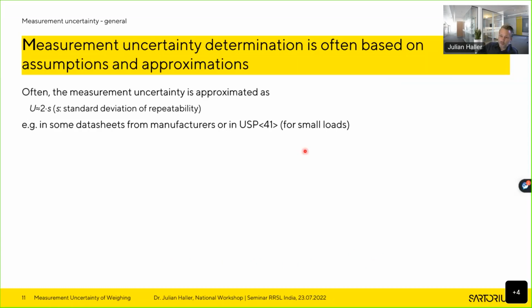And what you've probably seen in, for example, data sheets from manufacturers, or if you're familiar with that in chapter 41 of the USP for small loads, is that as a rough approximation of the measurement uncertainty, one just takes 2 times the standard deviation of a repeatability measurement. So this is a pragmatic approximation, but it is of course not the whole truth. So that you're just aware, often something like this is stated, but this is just a rough approximation.